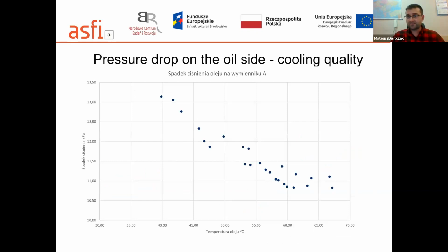I said that we measured a lot of data. So, the pressure drop on the oil side. The heat exchanger on the oil side is a resistor, of course. So why is it important to ensure a low pressure drop? The exchangers selected by us have a low pressure drop. Even with cold oil, at 30 degrees, we have below 15 kilopascals. The exchangers used by manufacturers have a drop between 40 and 100 kilopascals.